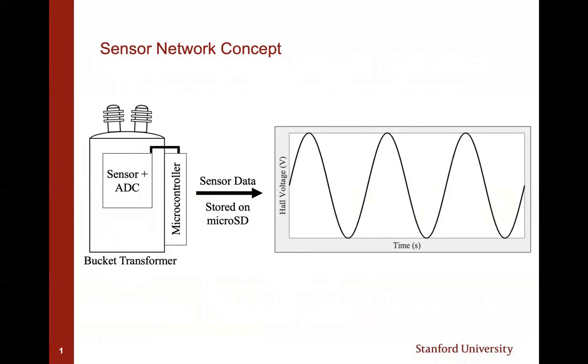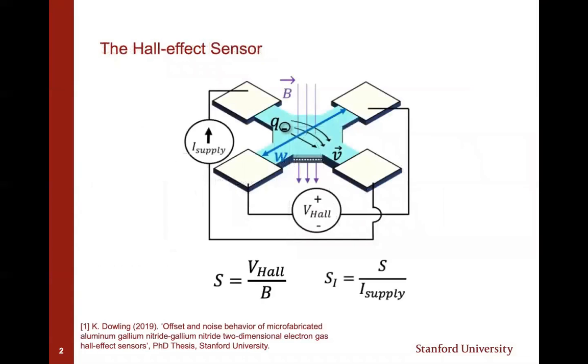In our lab, Hannah Alpert et al. demonstrated the promise of InAlN sensor recovery for temperatures as high as 600 Celsius. Our plan was to mount these sensors onto sensor tester boards, STBs, that had an onboard analog to digital converter. Data was sent from the STB to a microcontroller mounted outside the transformer, where data was stored on a micro SD card. The measured Hall voltage is directly related to the magnetic field strength and therefore the current inside the transformer. Hall effect sensors have a great deal of potential for use in transformers because they are low cost, easy to integrate, and linear over a wide range of magnetic fields.